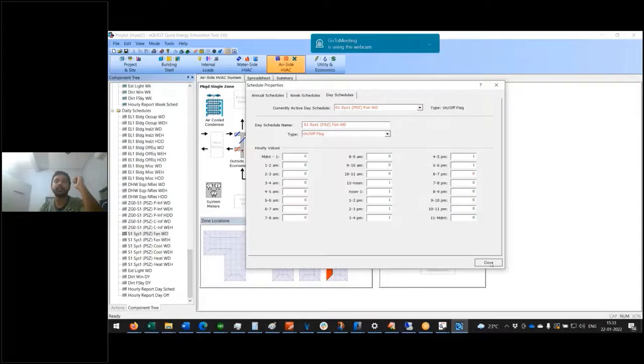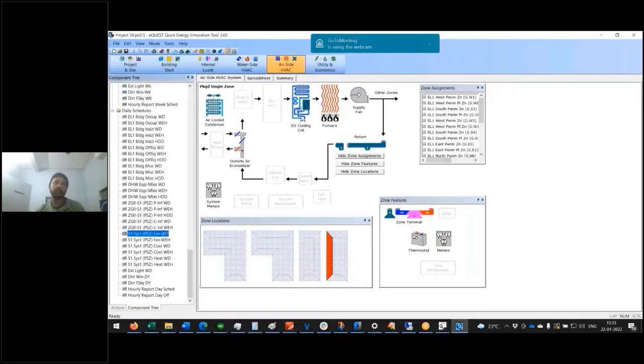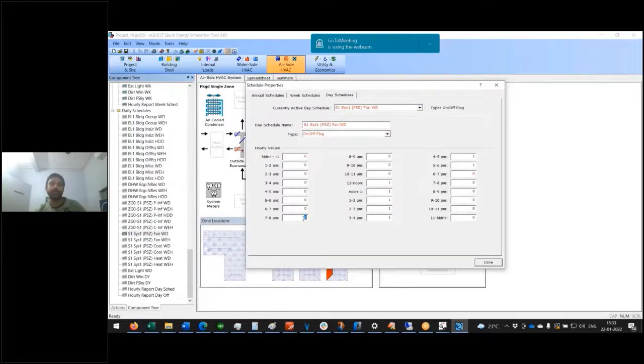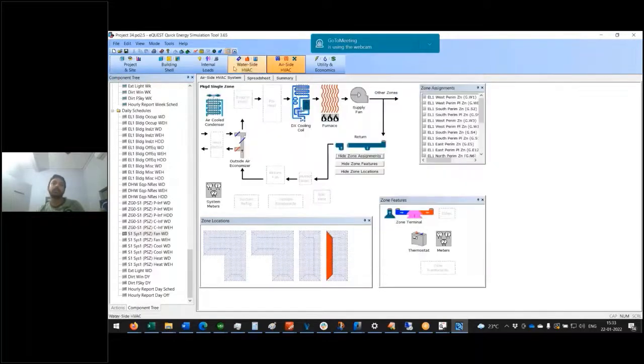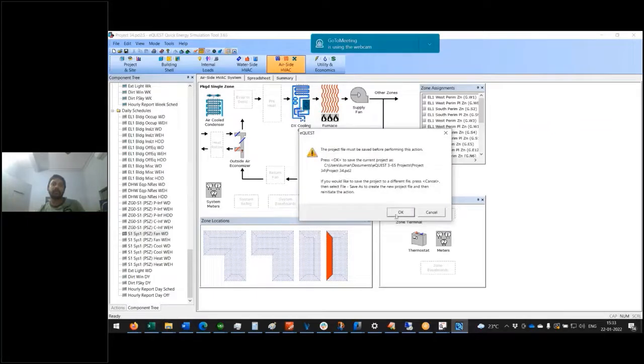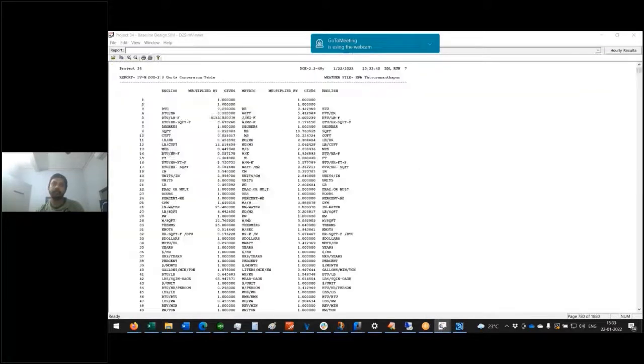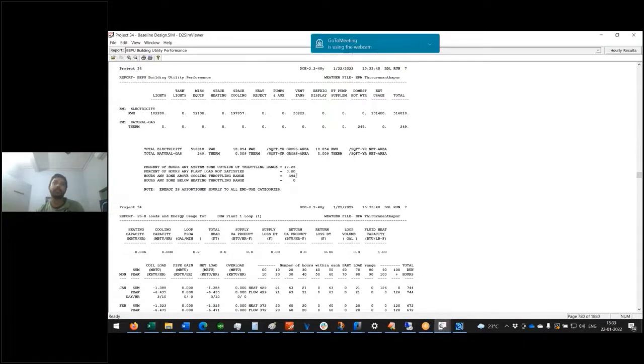with when the fan is in operation. It starts at 11 o'clock, but as per our setpoint of 76, when the fan is off, that means there's no supply air. So even if your cooling coil is on, it doesn't matter; there's no supply air going into the space. So be very careful, because even a slight mismatch here will end up causing throttling range. So I just changed that back to 1 again to start at 7, and there you go, it drops down to 492.